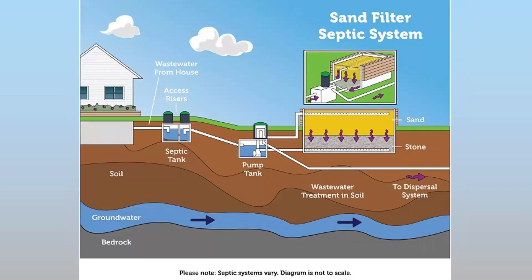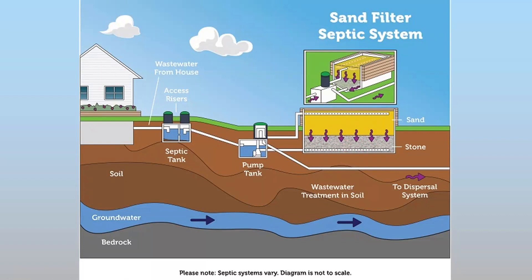Here's a schematic of an above-ground sand filter, which is partially above grade. An advanced treatment unit feeds water up into the sand filter — essentially a boxed mound using similar technology, but providing adequate depth of specialized sand to treat wastewater before it enters the natural soil. These are particularly useful where there is a very high water table and can be very effective at treating wastewater.